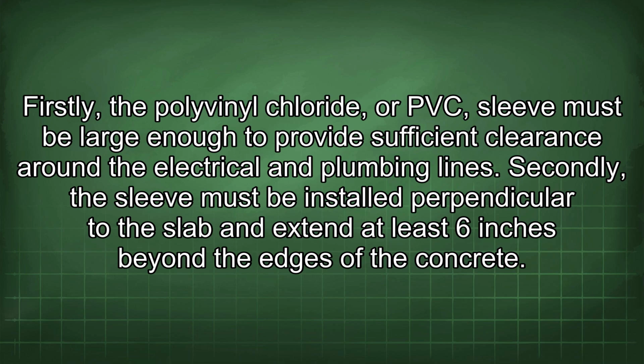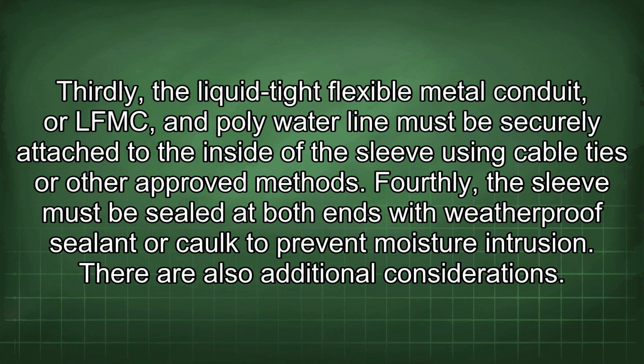Firstly, the polyvinyl chloride, or PVC, sleeve must be large enough to provide sufficient clearance around the electrical and plumbing lines. Secondly, the sleeve must be installed perpendicular to the slab and extend at least 6 inches beyond the edges of the concrete. Thirdly, the LFMC and poly water line must be securely attached to the inside of the sleeve using cable ties or other approved methods. Fourthly, the sleeve must be sealed at both ends with weatherproof sealant or caulk to prevent moisture intrusion.